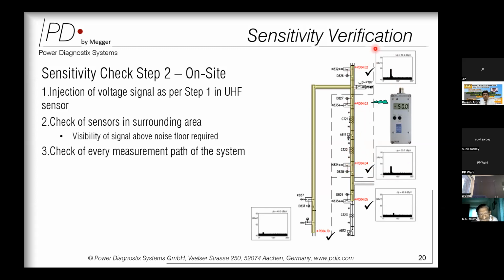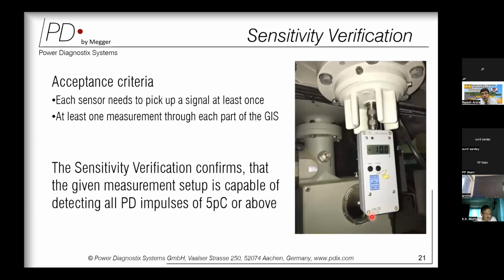5 PC, any of the nearby sensor will respond, and hence we can say the path between point number 2 and point number 4 is clear to capture 5 picocoulomb partial discharge. This way we will inject pulse to the next sensor, we will measure at correspondingly the next sensors in nearby vicinity, and we establish an acceptance criteria that this particular GIS is sensitive enough to capture 5 picocoulomb and above partial discharge if happening anywhere inside the GIS. So we have set up an acceptance criteria for the GIS.